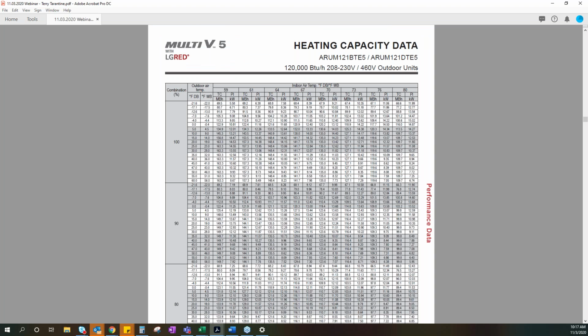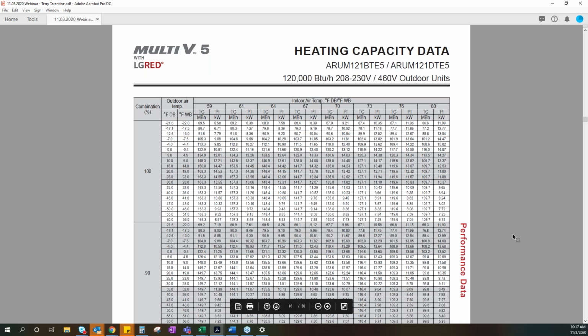Okay, if we move to the next one. Here's the VRF. You'll see that the VRF has very similar outputs to the water source. In this particular slide, if you look at the very top, you'll notice that this manufacturer has listed their capacities all the way down to negative 21.6 degrees. And at that negative 21.6, it's still putting out almost 68,000 BTUs of heat, more heat than the unitary 10-ton did at 5 degrees. And if you look at the top of the shaded column, there you'll see the 5 degrees, and we carry that over to the 70 degrees. You'll see that we're getting over 130,000 BTUs of heat output from an air source heat pump at 5 degrees.